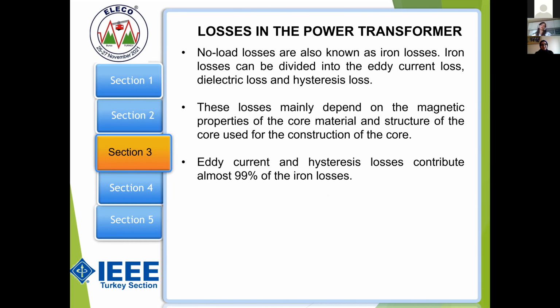When we talk about the no load losses, these are also known as iron losses, or sometimes we call them core losses. These losses can be divided into two parts: eddy current losses and hysteresis losses. We have a third one, dielectric losses, but its share is only 1%. All of these losses mainly depend on the magnetic property of the core material, the lamination of the core, and the structure used for the construction of the core. As I told, the main parts of the no load losses are eddy current and hysteresis losses, which contribute almost 99% of the iron losses.